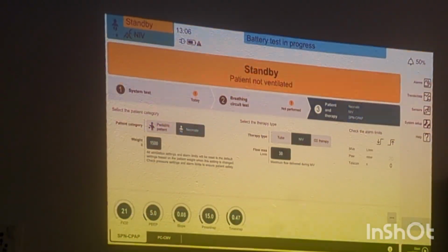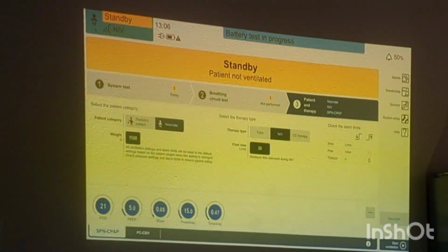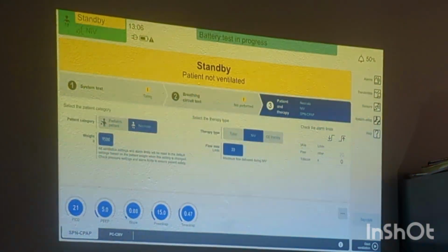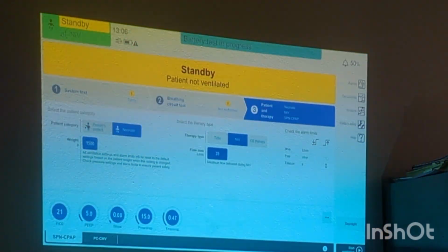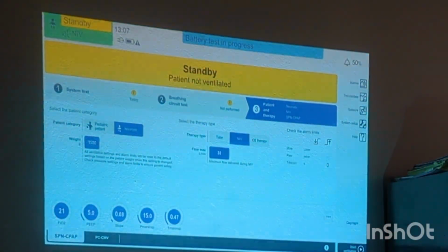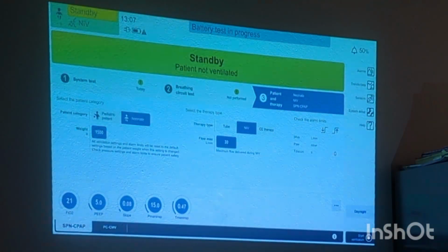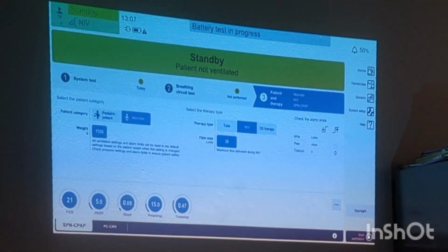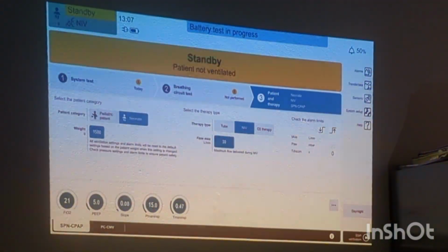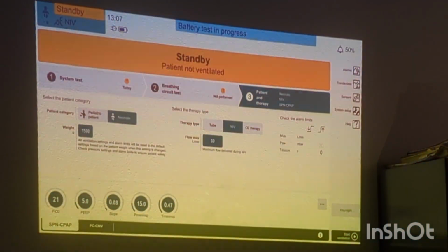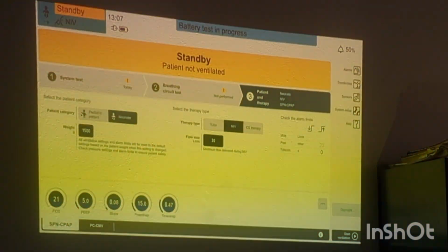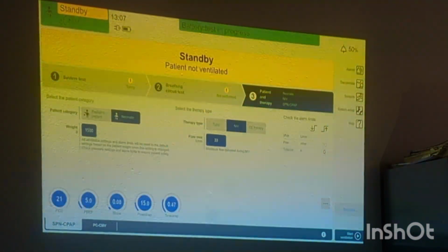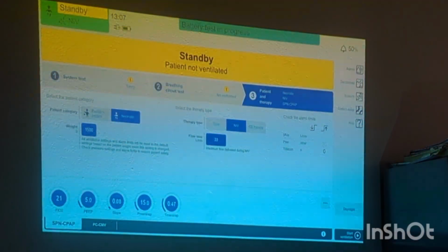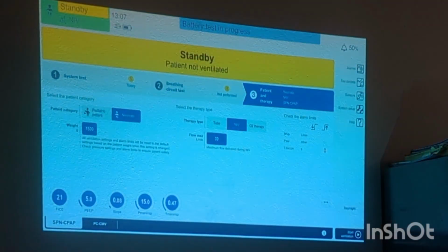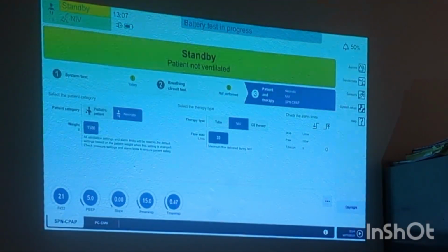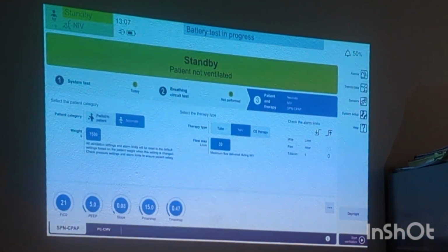So whatever tidal volume it is showing, suppose your device is showing 2 ml, definitely that is not going to your patient. What your patient is getting is not sure, and the expired tidal volume will not be monitored properly, so you will get a lot of alarms. Just to get rid of these alarms, they have selected this mode for when you are using prongs and mask. So you will not get a lot of unnecessary alarms.